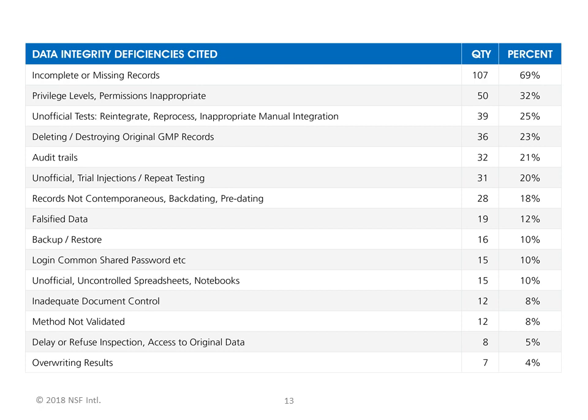Now, in and of itself, manual integration is not a problem if it's used sparingly and under appropriate controls and with appropriate approvals. When manual integration is used rampantly and there's no controls for it, then that becomes a problem, and the FDA will cite you for excessive manual integration with no approval or no procedure to guide that type of integration.